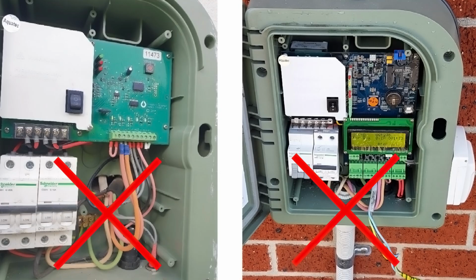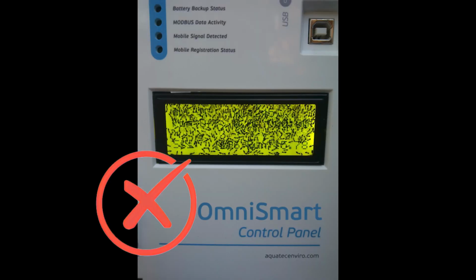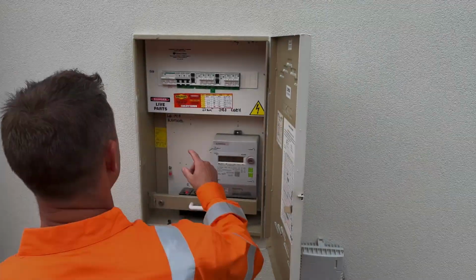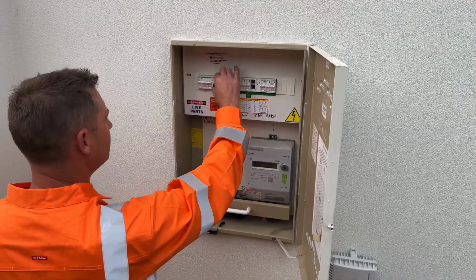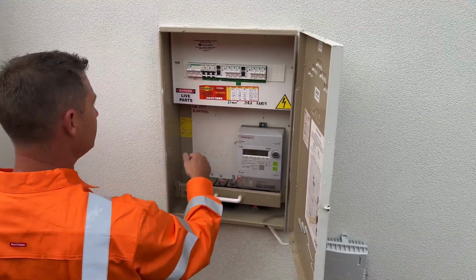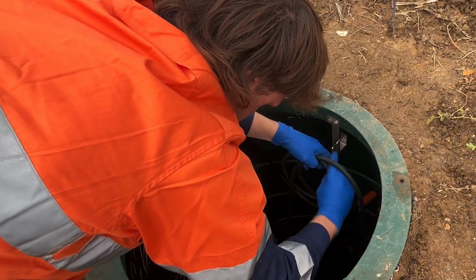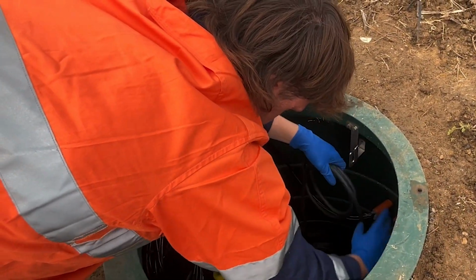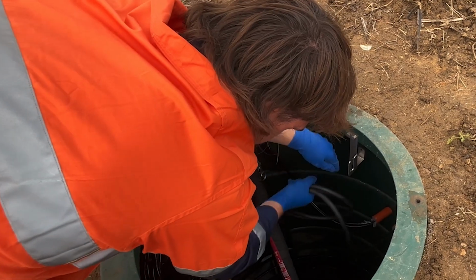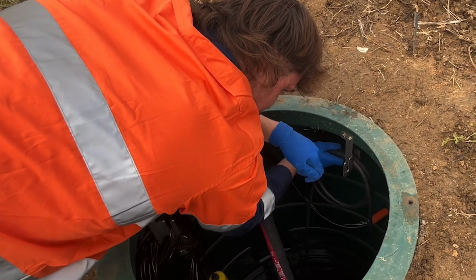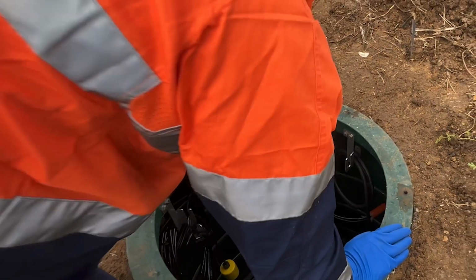Avoidance of ingress into the control panel is not only referring to moisture, but also insects. If the above steps are not followed correctly, insects can also penetrate the control panel seal and affect the electronics inside the unit. A dedicated circuit breaker needs to be installed in the distribution panel of the building to safely supply power to any Aquatec pressure sewer system. There should be a maximum of 2 meters of excess cable inside the well. Excessive amounts of cable left inside the well can be difficult to tether and ultimately ends up being held by cable ties.